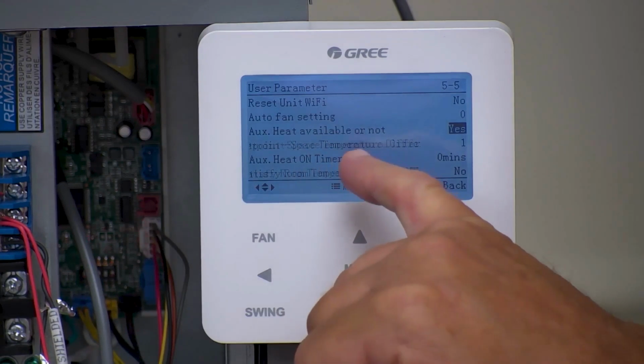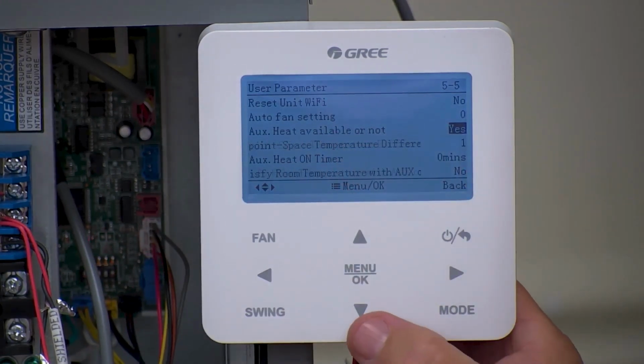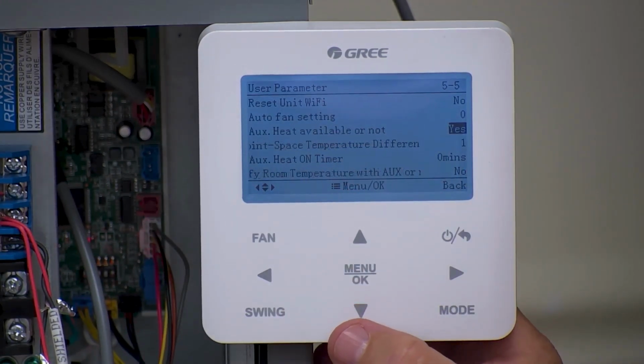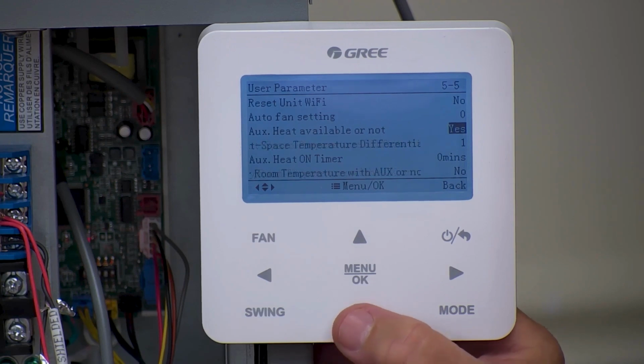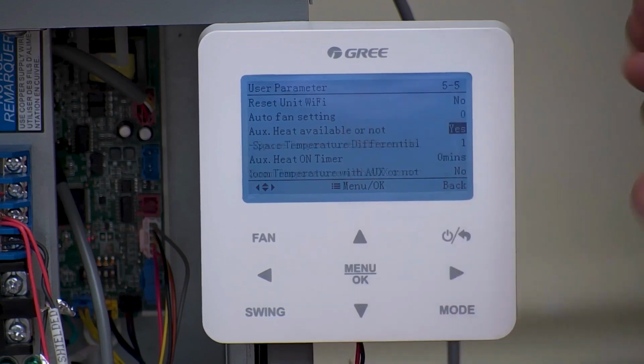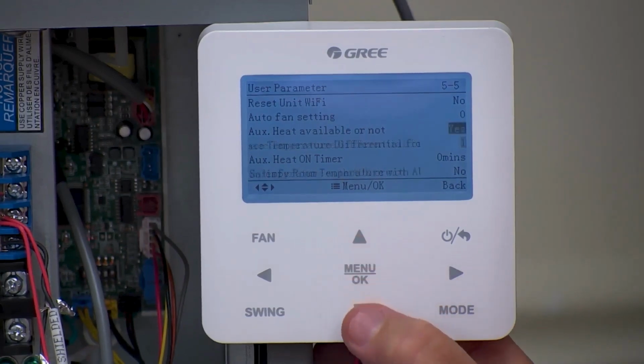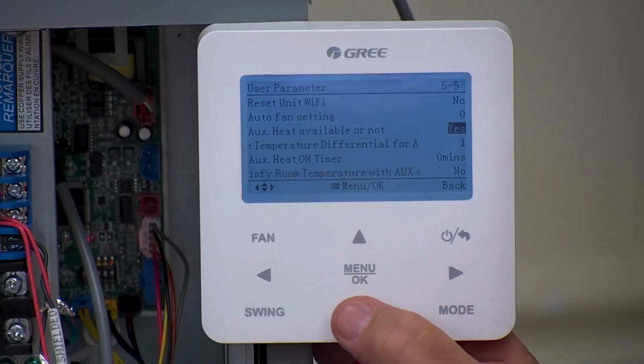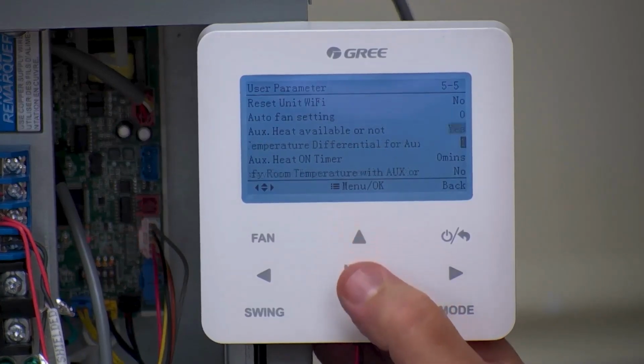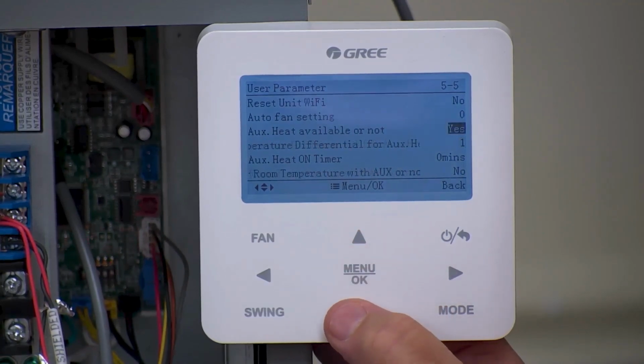Auxiliary heat available or not, yes or no. Like I said, if you got electric heat, that's going to automatically populate yes. If for some reason it doesn't, it should at least give you that and you can set it. Space temperature differential. So it's kind of a weird setting for you. And if you notice I'm going up and down with the arrow buttons, that's because these things time out rather quickly and you're going to lose your page.